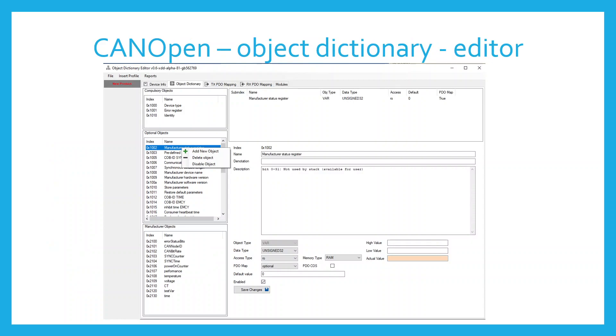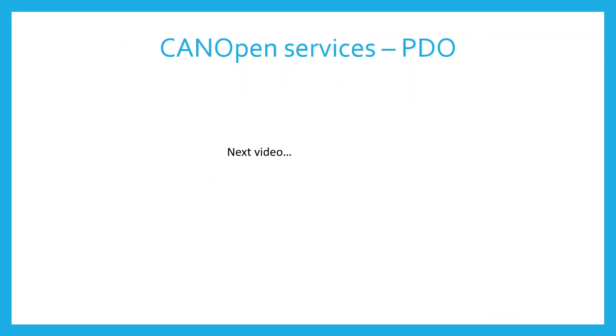As you can see here in the open source EDS editor, some objects are mandatory and others are optional. This configuration file is also known as an electronic data sheet, so it has an EDS extension. The configuration editor can generate C source and header files which are part of a CanOpen stack. Now I will move to the PDO services in the next video.